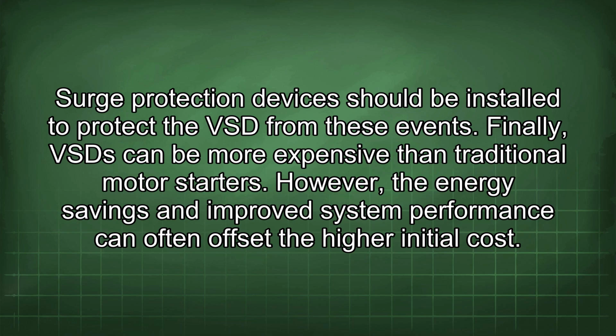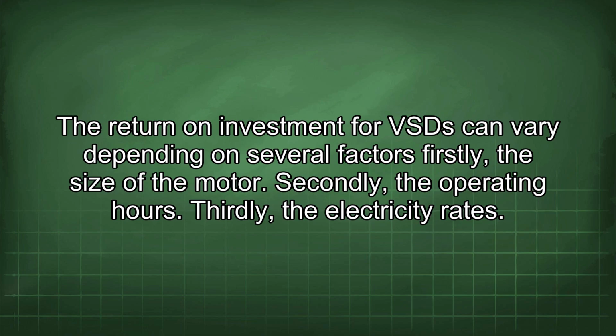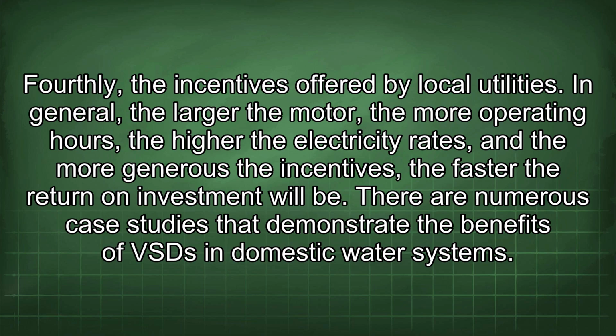Finally, VSD can be more expensive than traditional motor starters. However, the energy savings and improved system performance can often offset the higher initial cost. The return on investment for VSD can vary depending on several factors. Firstly, the size of the motor. Secondly, the operating hours. Thirdly, the electricity rates. Fourthly, the incentives offered by local utilities. In general, the larger the motor, the more operating hours, the higher the electricity rates, and the more generous the incentives, the faster the return on investment will be.